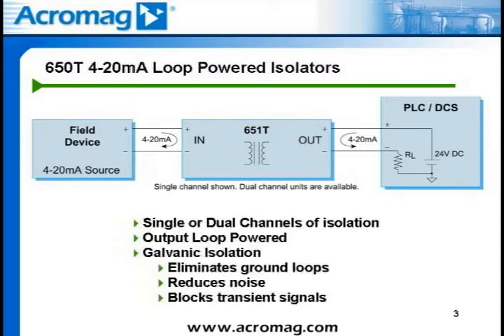Location is also not an issue in this application. Since the output from the isolated transmitter and the power source share the same two wires, these modules can be placed anywhere between the field device and the PLC. Since both the input and output signal to the isolated transmitter are 4 to 20 milliamps DC, location of the device is not critical.